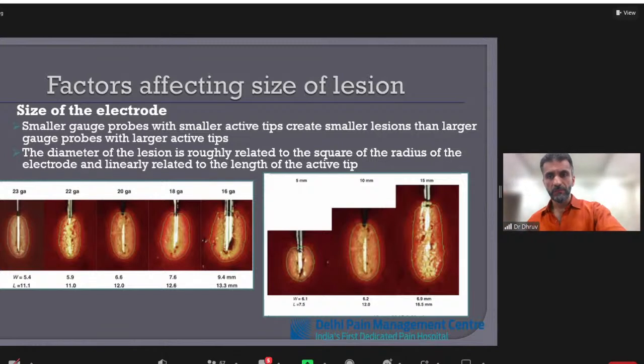Most of them have a direct relationship. For example, if we increase the size of the electrode, the lesion size will increase. If we increase the temperature, again, the lesion size will increase. If we increase the time for which we are producing a lesion, the lesion size will increase. But it is not that we can do it indefinitely, because what eventually happens is, when you start, the needle gets heated, the tissue gets heated, and after a point of time, if we keep on doing it, there is a charring or the burning of the tissue, which will act as a hindrance for the transmission of temperature across the tissue. Hence, the lesion size will be limited.